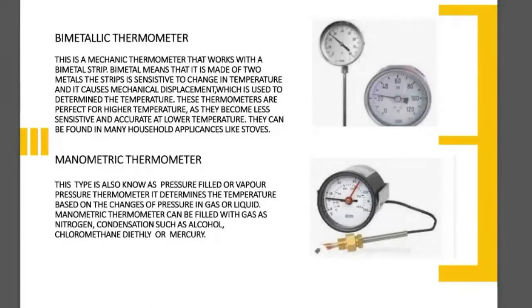So last is a manometric thermometer. This type is also known as a pressure filled or vapour pressure thermometer. It determines the temperature based on changes of pressure in a gas or a liquid. A manometric thermometer can be filled with a gas such as nitrogen, or a liquid such as alcohol, chloromethane or mercury.